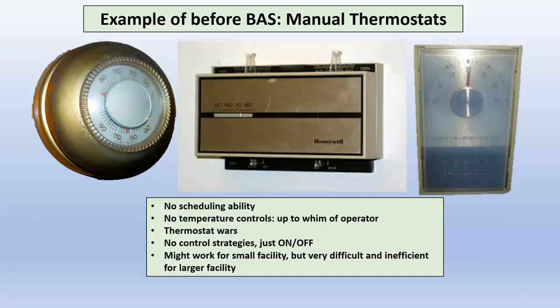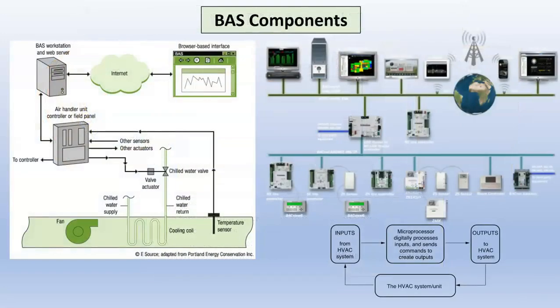They might work okay for a small facility, but if you get anything very large, it's going to be difficult to use these. They're not very efficient and they're hard to deal with. So a building automation system is comprised of many components. Let's say you have an HVAC system. The points inside that HVAC system, such as, let's say, the fan or the cooling coil, temperature sensor, there's a bunch of different things that you want to measure in there. Those are going to leave that and go to an input module or an I/O module. And from the module, it's going to go to the controller, to the brain of the BAS.